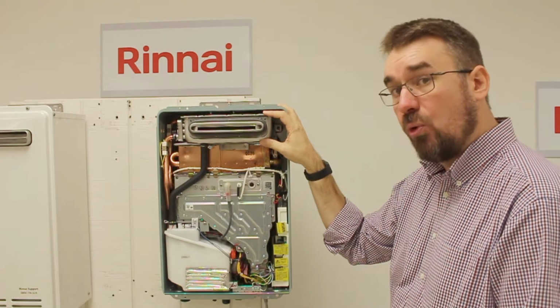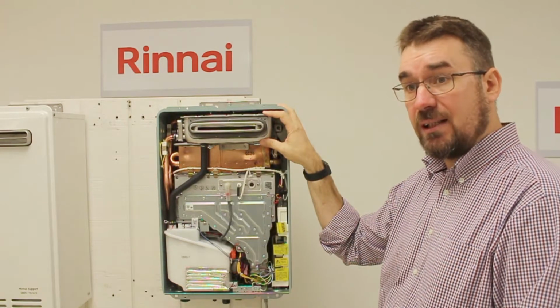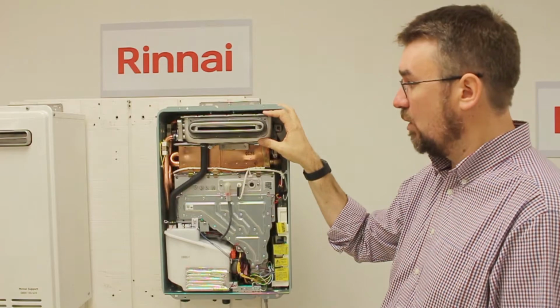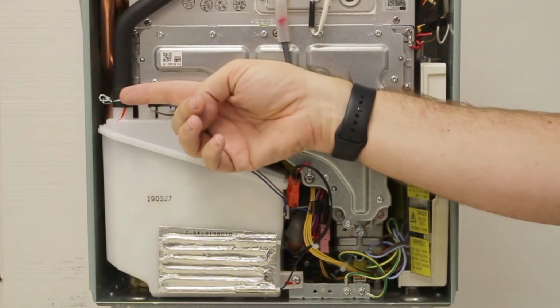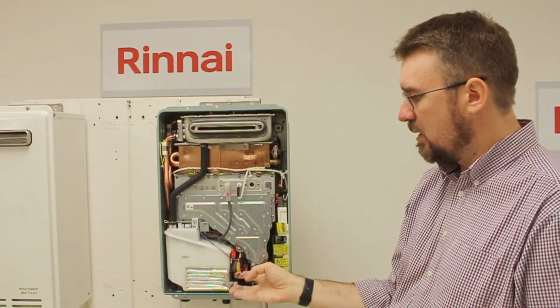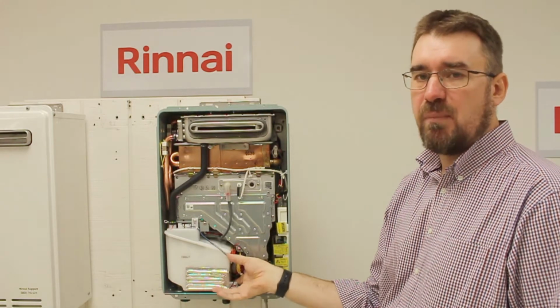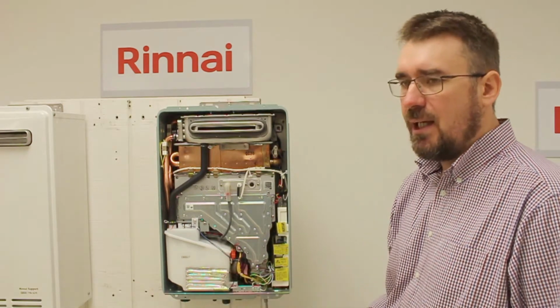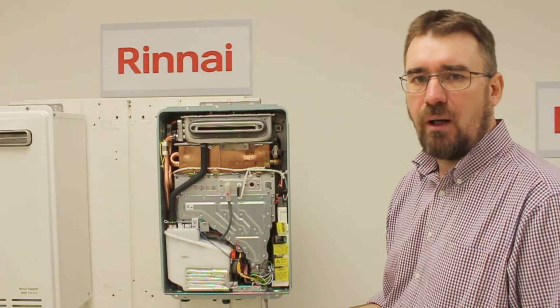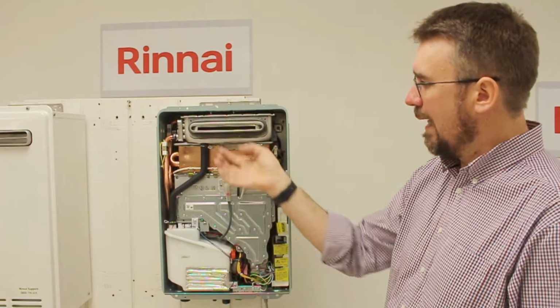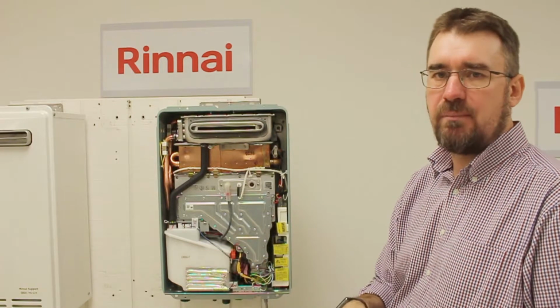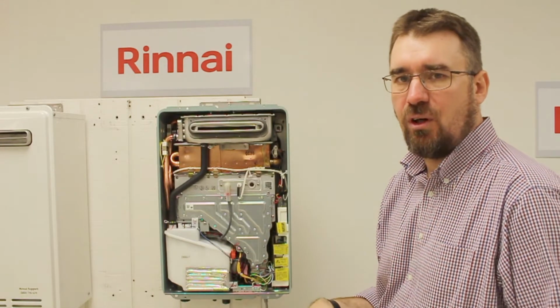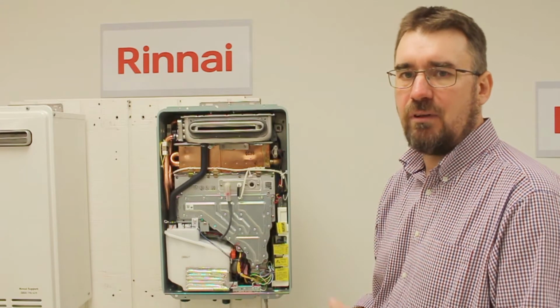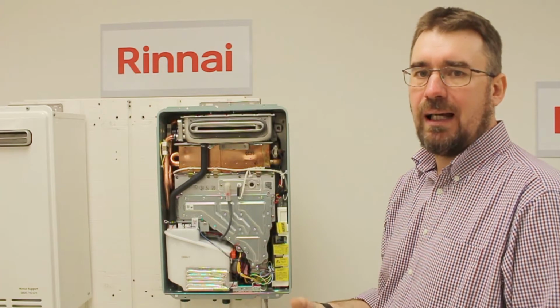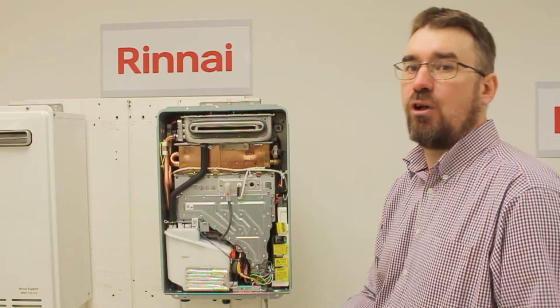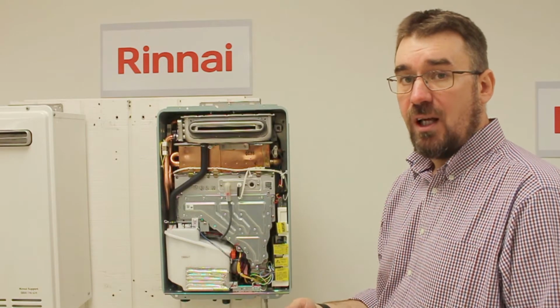By preheating that water, it's going to cool the flue gas down, then we'll get condensate forming. The condensate forms and drains down into this item here, which is a condensate collection and treatment bottle. What we've got in here is a treatment media, which is fundamentally lime chips. Acidic condensate runs down into the bottle, hits the lime chips, and that breaks the lime chips down over time. As the lime gets broken down, it's alkaline and acid mixed together, and you neutralize the acidity of the condensate.